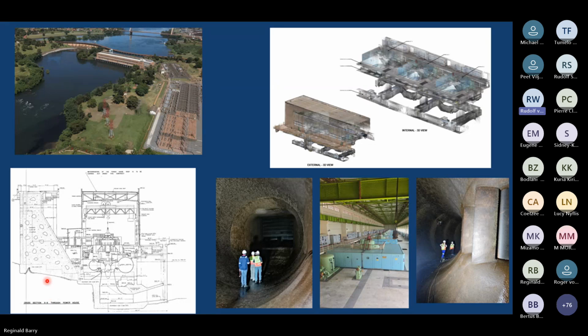A very important aspect when designing the hydropower plant is that you need to be able to maintain it. You need to be able to take out the turbine and the generator, so there's an overhead crane, and then all sorts of auxiliary systems within the powerhouse. On the top right corner you see a scan of the hydropower plant that was done so it could be used in the design. We're looking at the rehabilitation of this hydropower plant at this stage.